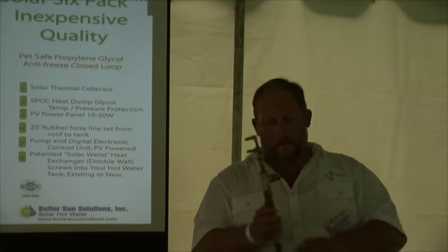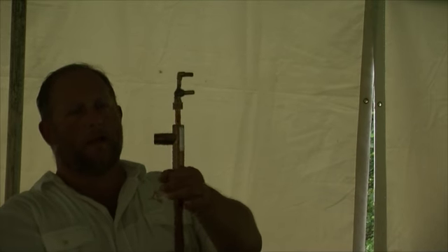All right. So this allows you to turn your existing tank into a solar storage tank by putting this heating element inside the hot water out of your tank, right off the top of the tank. It threads right off to the top of the tank. All right. Now this becomes your hot out. Normal plumbing goes off to your fixtures, and these two are your supply and return to the solar.